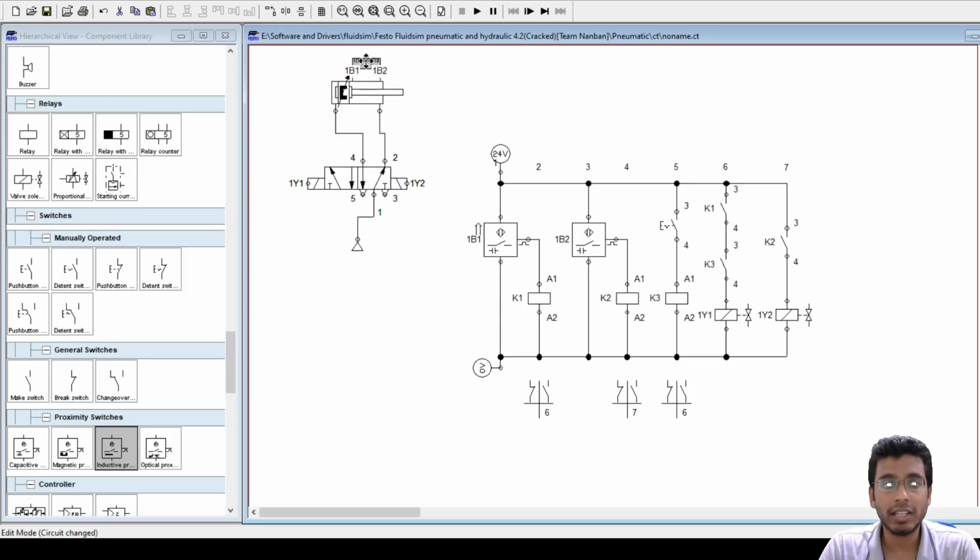If the limit switch is there, it will be placed on the line, so it will obstruct. Of course, that roller valve will come into the line of your piston rod, so that whenever the piston rod comes, it has to go and hit that. Otherwise, if there is no contact, your limit switch will not give any output, because it is a contact type. However, in case of your proximity sensor, you do not have to make any contact. It can be just placed over the cylinder itself.